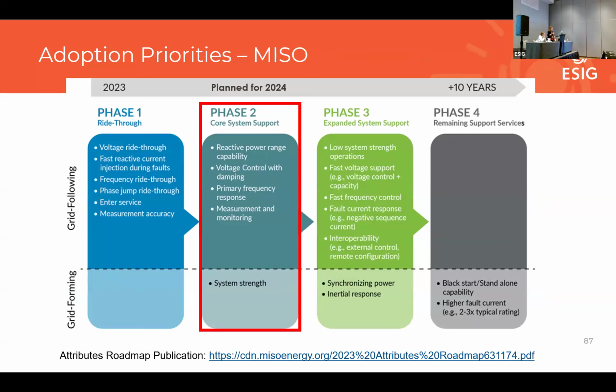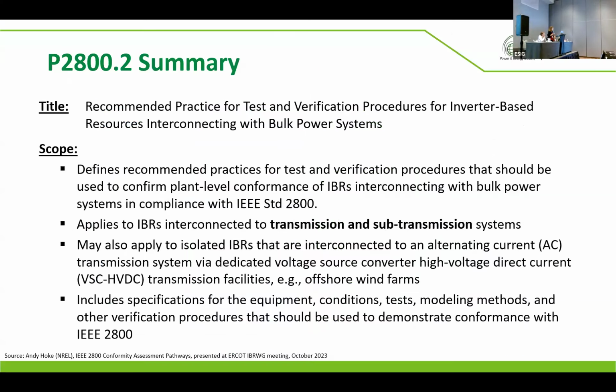MISO is currently in the process of adopting 2800. They are doing it by detailed reference. So basically, clauses of 2800 will apply where they see gaps in the existing interconnection requirements. And so phase one has been completed already, where they looked at voltage ride-through, fast reactive current injection, things like that. And now they are focusing on reactive range capability, voltage control, damping, primary frequency response, measuring and monitoring. So ERCOT is currently also undergoing a similar process. I just wanted to show one as an example.